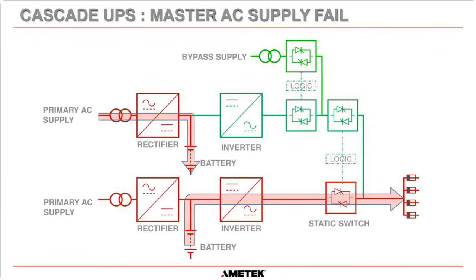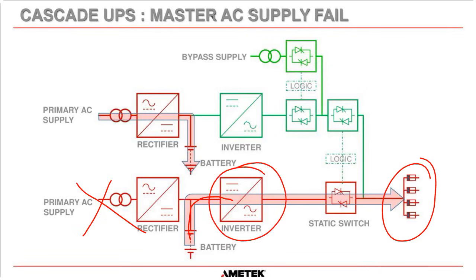So if we lose power on a cascade system, then as always, the system goes on to battery. We want to keep these load circuits supplied by an inverter because the inverter gives us clean and regulated AC power out to your load circuits. We're protecting those load circuits as much as we possibly can.